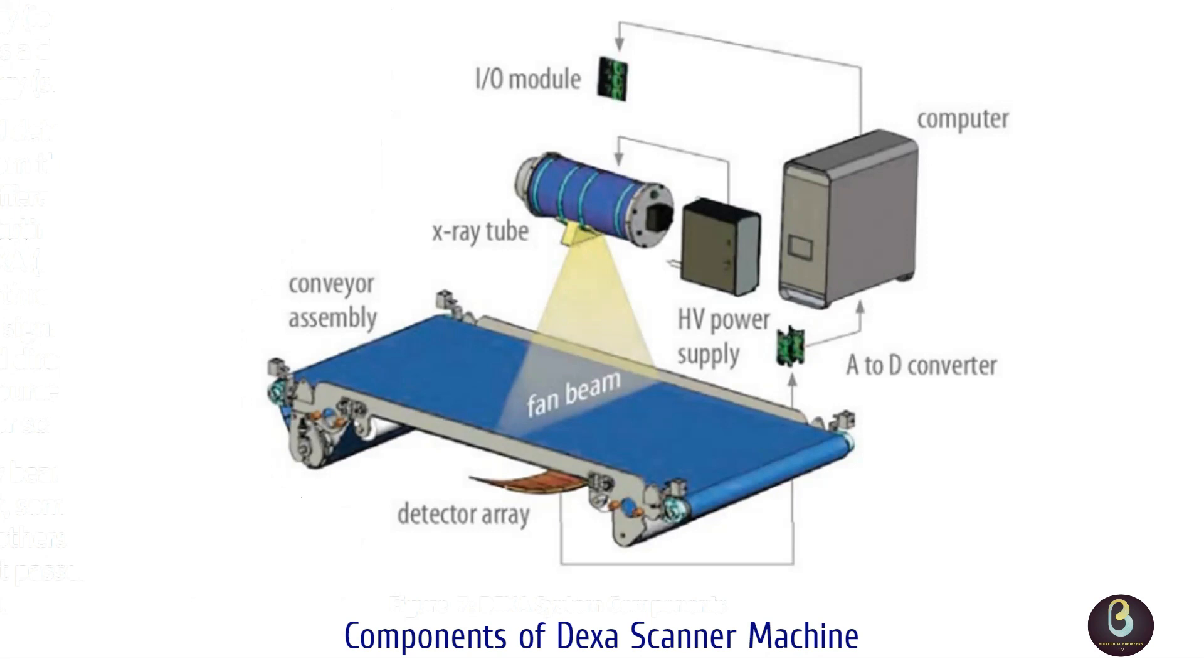Modern X-ray tubes consist of a glass envelope, a filament cathode, a copper anode, and a tungsten target. The cathode, which is the source of the electrons, is a tungsten filament, heated to incandescence by an electrical current.